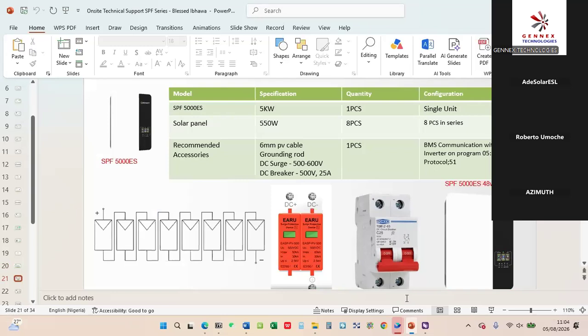You can get this, but one thing to take note of is when buying your surge, check the voltage range. Sometimes we are installing a machine that can take a maximum of 500 volts, but we put a surge rated for 1,000. It's not going to work properly. If there's a surge that comes in, it will pass through because the device is doing its job as rated for 1,000 volts.